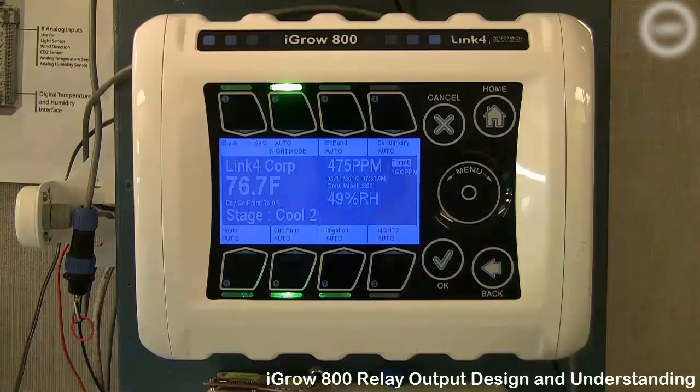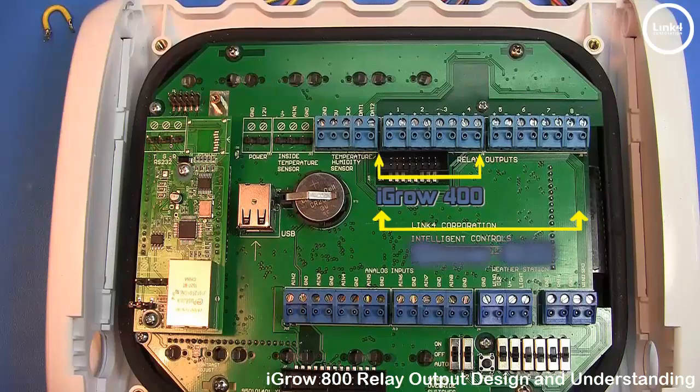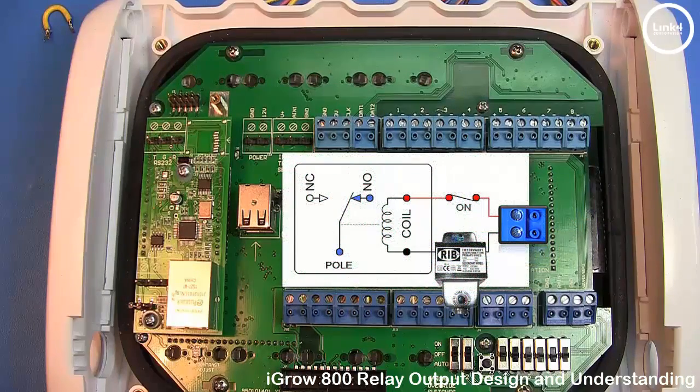In this video we will talk about the relay output design and understanding on the iGrow 800 series controller. The iGrow 800 series has four or eight output relays that are provided as dry contact switch closures. If an output is activated to on, the switch is closed and shorted; if it's activated to off, the switch is open with no continuity between the positive and negative terminals.